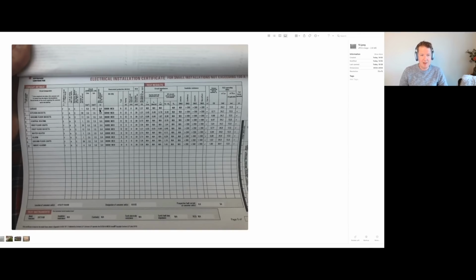And here we can see the garage circuit is on a 6mm squared cable with a 4mm CPC. So that indicates to me that probably it's twin and earth cable type A wiring here, going from the house consumer unit to a junction box outside, and then probably armored cable from there.